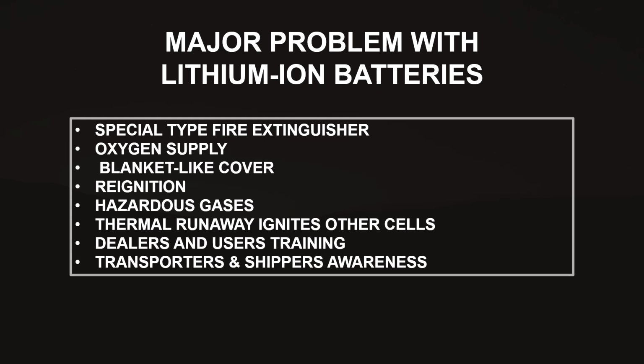A significant problem with lithium-ion batteries is that in case of fire, they can only be put out using special fire extinguishers known as AVD type, aqueous vermiculite dispersant. The oxygen supply needs to be cut off to restrict the fire, but that does not mean the fire will go out completely or that explosions will stop. A blanket-like cover is required, but reignition is highly possible despite covering and cutting off oxygen. The hazardous gases emitted during a fire are dangerous enough to affect a person's lungs or eyes, but this is not well known to many people who deal with fires or are at the scene trying to put them out.